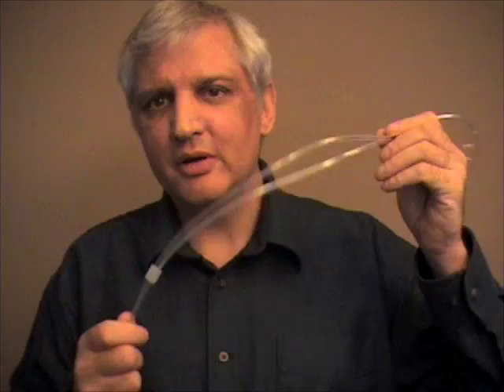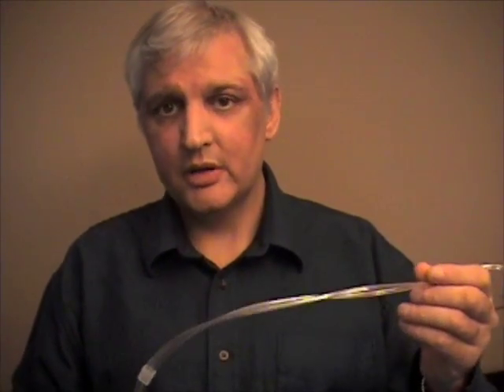Something very odd is that some suppliers in Toronto give people cannulas that only support up to six liters a minute. I've actually met people whose doctors prescribed them between 6 and up to 15 liters a minute of oxygen, but they've only got regular flow cannulas. So they think they're on 10 liters a minute but they're only getting six. So if you're ever supposed to go above six liters a minute, make sure you've got a high flow cannula, otherwise it defeats the purpose.